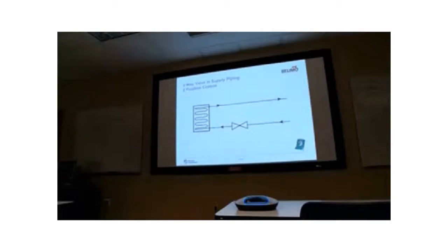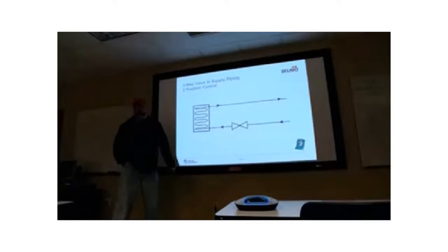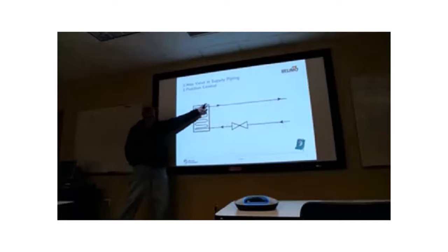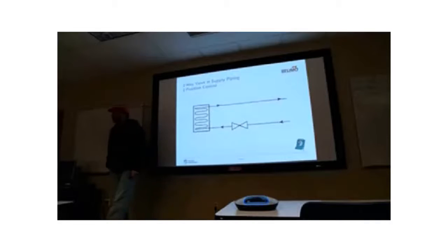Too many. In supply? Yeah. Really? It shouldn't be, but. Are they two-position valves, or are they proportionally controlled? Well, if it's when they put them in wrong. Well, I'm not sure if they put them in wrong, but the thing is, yeah, we normally don't do that, right? I mean, where are they normally? They're normally on this side, right? They're normally on the return side.